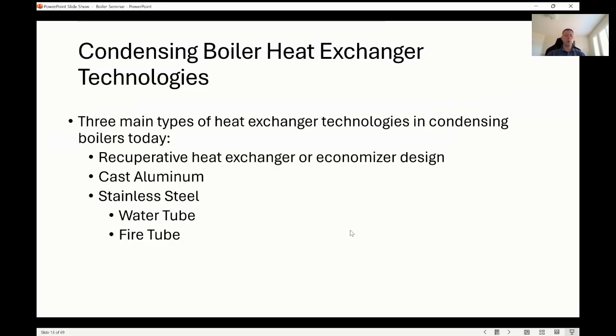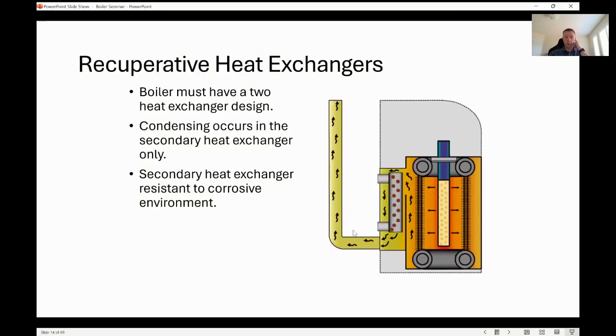When you're selecting a condensing boiler, there are a lot of different technologies out there these days. There are three main types of heat exchangers, and that's the prime thing you're looking at with a condensing product. There's more than just these, but I think these are the prime ones out there. There's the dual heat exchanger, or recuperative heat exchanger, which is kind of like two heat exchangers in one, an economizer pulling that extra heat out of the stack. Cast aluminum is a popular choice, and of course there's stainless steel. I think most manufacturers have a stainless steel product out these days, and within stainless steel there are water tube and fire tube type heat exchangers. The first one I want to look at is the dual heat exchanger or recuperative heat exchanger design. With this, you're going to have two heat exchangers.